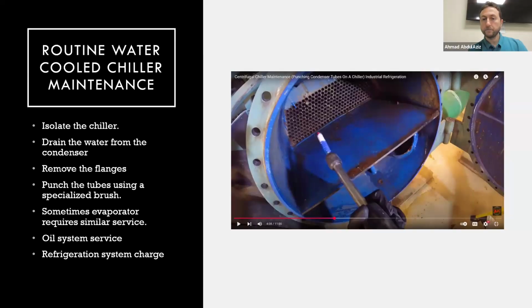Yes, and then — I don't think there's a video with this, but this is just showing, this wasn't a bad little video. I didn't plug it in, but basically you see all the bolt holes — you drain that chiller, this is for water cooled. Then there's this little punch tool where you squeegee out the tubes, whether that's water in the tubes or refrigerant in the tubes. You're just cleaning them to make sure the path for the refrigerant or water is clean. I remember going to a job site when I worked at Johnson Controls and seeing someone having taken apart this chiller, and I thought they must be a rocket scientist to do this stuff, but it's really a pretty simple thing to clean those tubes.